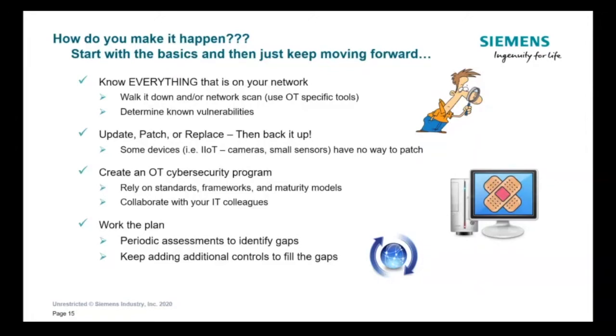One of the major issues that most customers don't realize or don't take into account, I think one of the biggest joke questions that I'll ask a customer is, when was the last time that you updated the firmware on your network switches or any of the other devices in your plant? Most end customers will probably laugh at me when I ask that question. Their response will usually be, well, when was it installed?